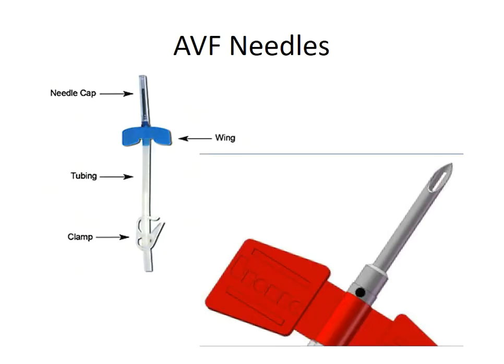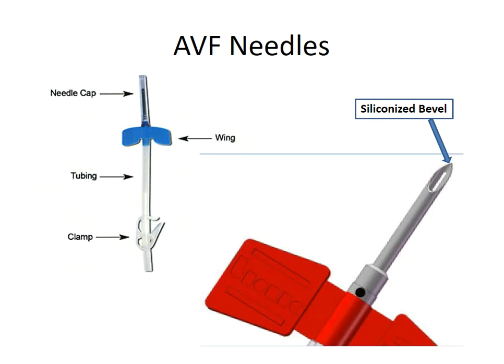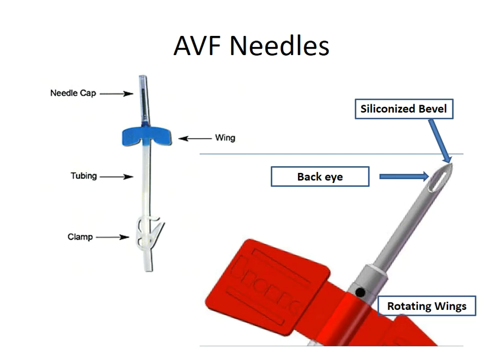The blood circuit starts from the arteriovenous fistula needles. The AV fistula needle has several components: a needle with a siliconized bevel and a back eye, wings, a tube, and a clamp. The needle features rotating wings.